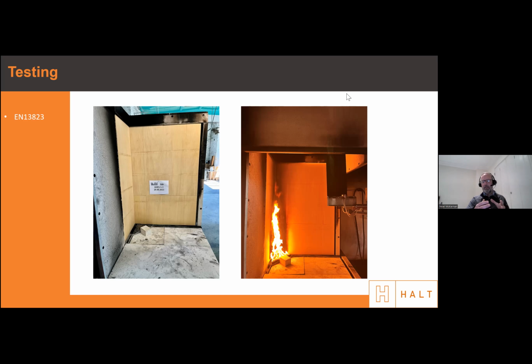If a fire is exposed on the outside of this timber, as the heat increases on the fire side, you will end up with a buildup of hot air and gases on the underside of that material. If the fire penetrates, you will get spread of flame on both sides of that material. If you just have a surface type treatment that gives you spread of flame protection, there's potential for the fire to increase and spread on the cavity side of the building if it penetrates the surface.